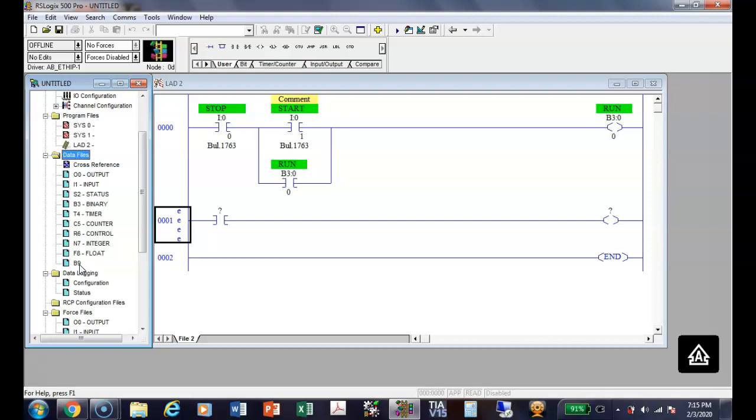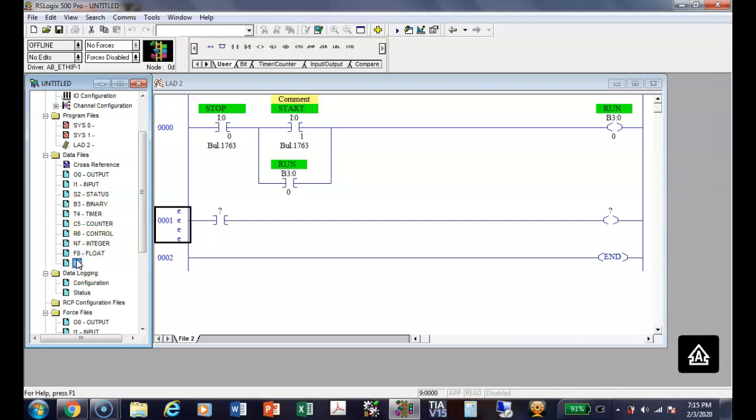Every one of these data files, except for timers and counters, we'll talk about that, has 256 different devices. That's why we have to specify B3, because that information is kept here. If I specified B9, then that information would be kept in this data file. So that's why we have to identify the data file number. I'm going to delete that.